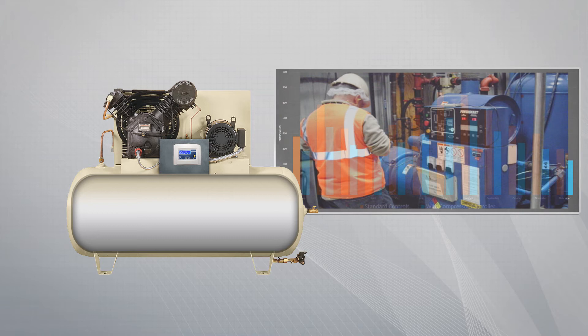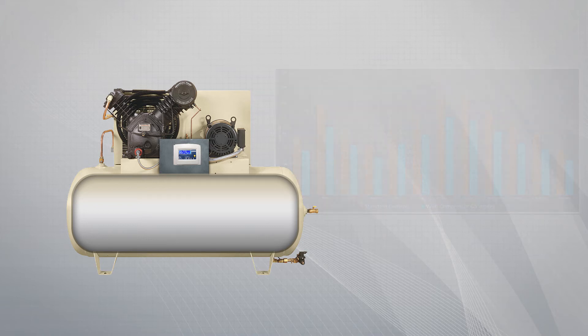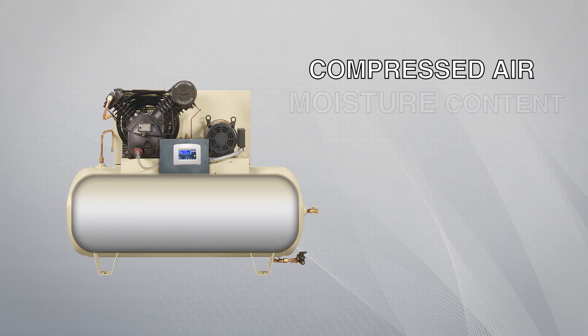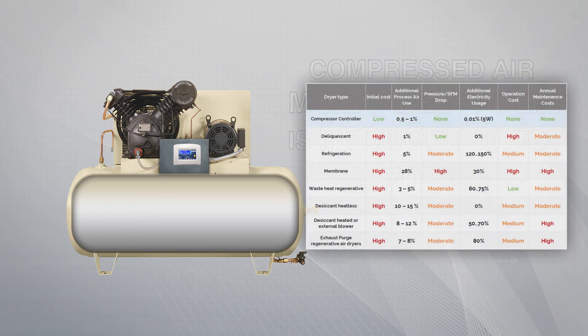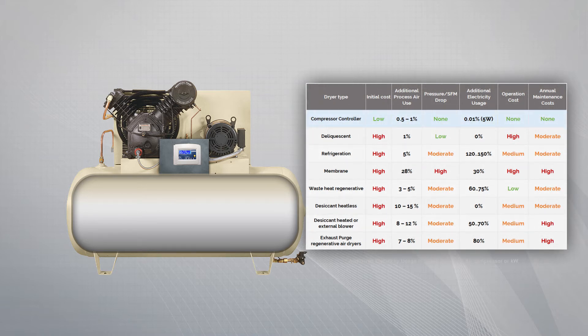Most importantly, with this approach, compressed air moisture content is reduced up to 70% without the use of additional dryers or conditioners. In operations where dry lines are critical and desiccant or other dryers are installed, the compressor controller provides a much less expensive way to dehumidify the air and reduce the energy and maintenance costs of compressed air operation.